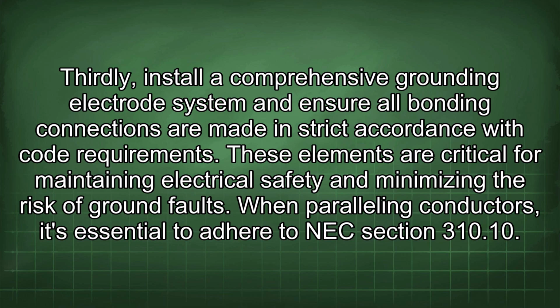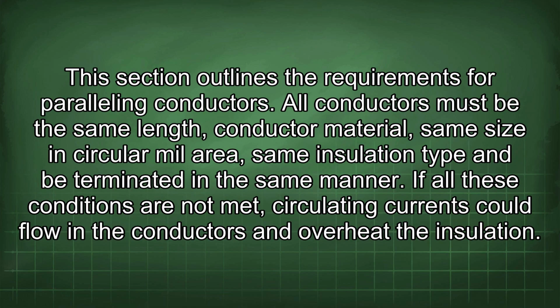When paralleling conductors, it's essential to adhere to NEC section 310.10. This section outlines the requirements for paralleling conductors. All conductors must be the same length, conductor material, same size and circular mil area, same insulation type, and be terminated in the same manner. If all these conditions are not met, circulating currents could flow in the conductors and overheat the insulation.